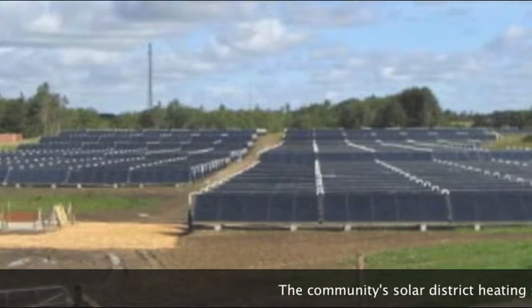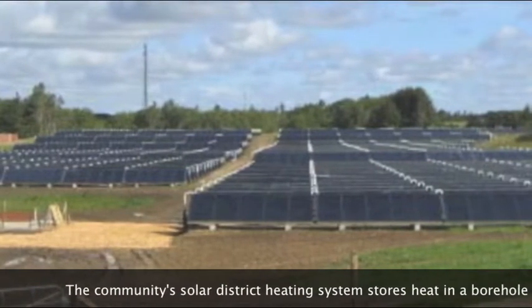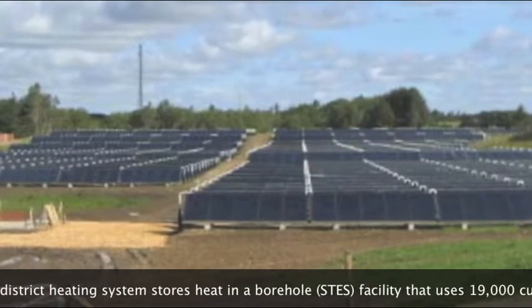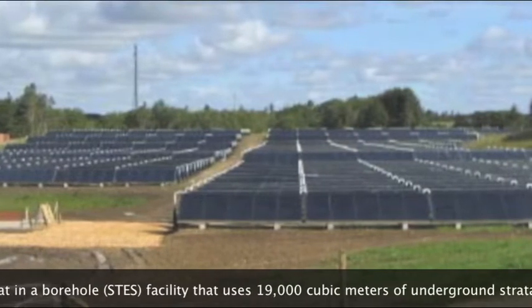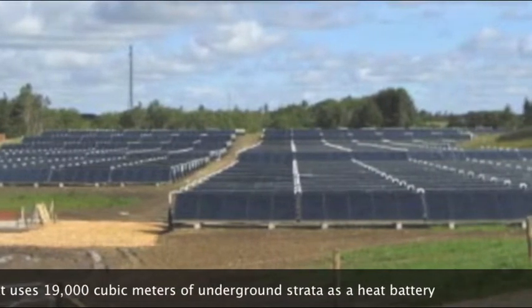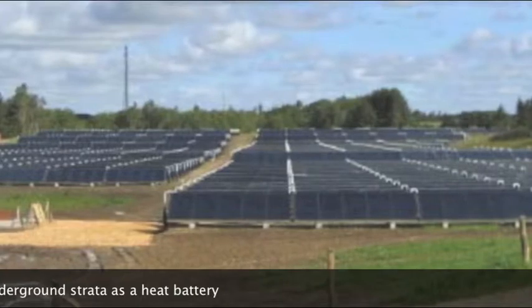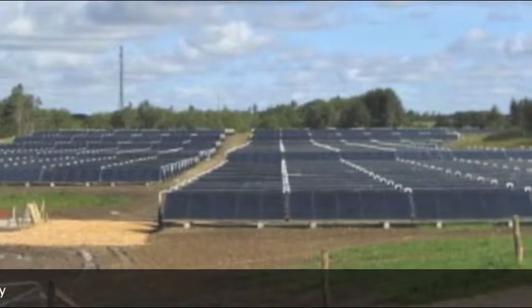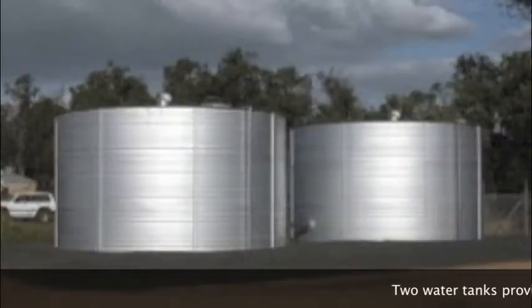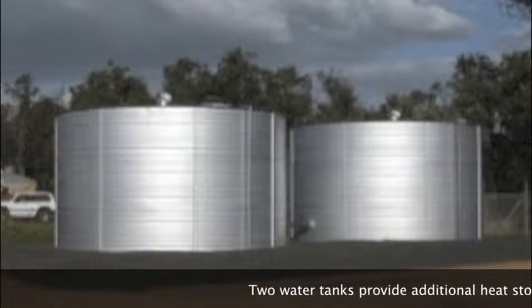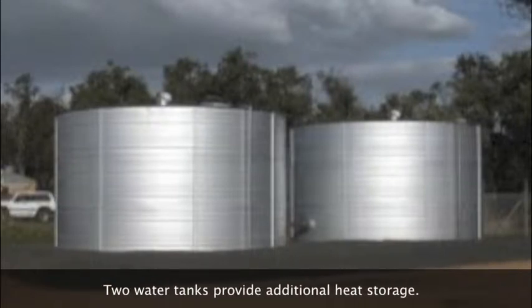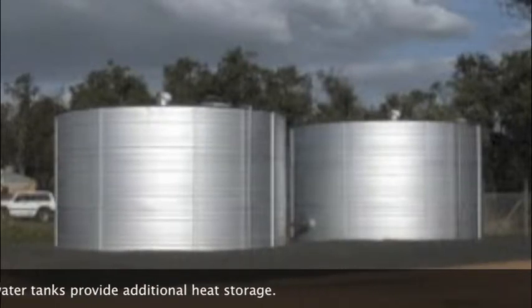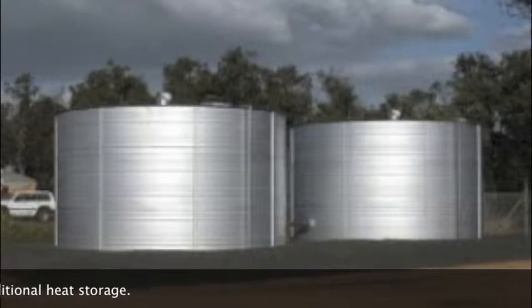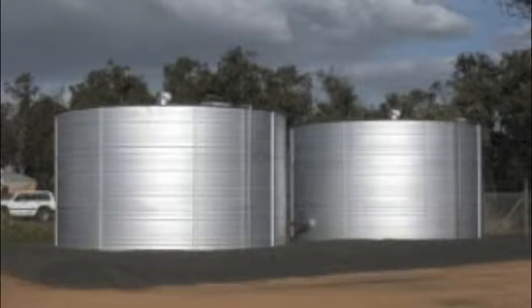Ballerup. The community's solar district heating system stores heat in a borehole facility that uses 19,000 cubic meters of underground strata as a heat battery. 2 water tanks provide additional heat storage. When extracting heat, a 1.5 megawatt heat pump boosts the temperature to 80 degrees Celsius for circulation in the district's heating loop.